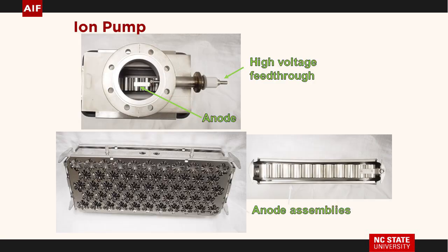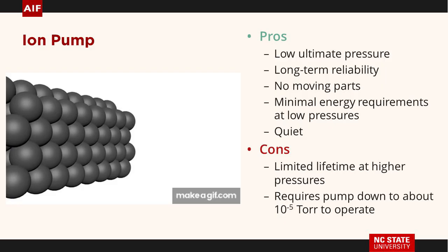And if you look down inside, you'll be able to see this. You'll see one of these assemblies. So it actually traps the gas. Great, no moving parts, low pressures. Can't run it at high pressures. Can't turn it on in air, won't work.